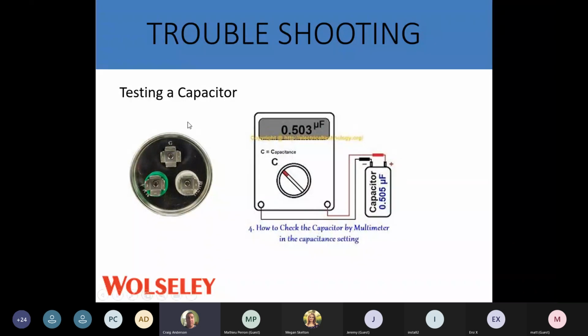We're testing the capacitor. They have actual meters that just do that, or most of your multimeters do it now. So this one has your compressor and your fan built in. It's a dual capacitor. One will say Herm, one will say fan, and then your common. You're going from your common to your Herm or common to your fan to do your testing. Fan's usually about 5 or 7.5, depending on the rating. And then your Herm runs from 25 to 45, depending on the size of the unit outside. So always check your capacitor.